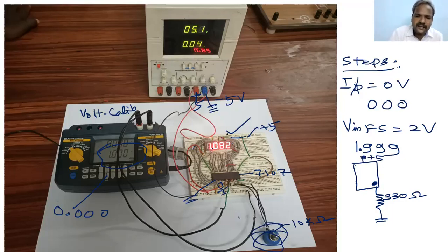Adjust the pot until you get 00 in the display. Then you apply 2 volt from the calibrator source. Check whether you get 1.99 or not. Then you adjust this input voltage until you get 199. Repeat this 2 to 3 times. Automatically it settles from 000 to 1999. Since we make this decimal illuminated, it is read as 1.999. Now the display shows 1.082 volts. Actually, we applied only 1 volt here, but the display gives 1.082 volts.